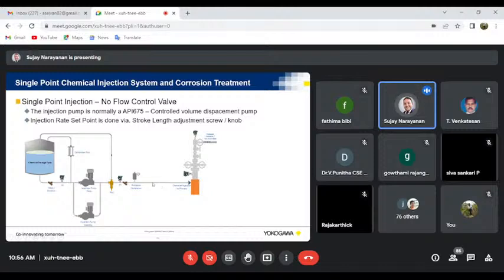You'll have a steady state flow over here. It acts like an accumulator to give a steady state flow. If you don't have the pulsation dampener, you will see this pressure gauge show 20 bar during the power stroke, and during the non-power stroke it will show 0, then 20, 0, 20, 0, 20. It will be fluctuating. But with a pulsation dampener over here, it will steadily show 20 bar. This fluctuation will not be there.